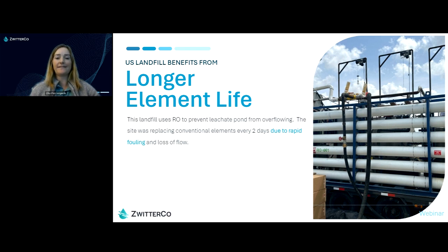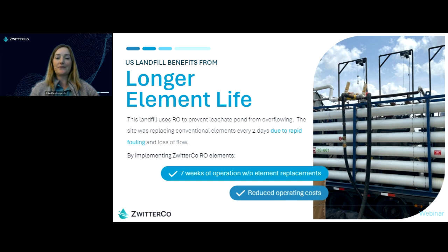Because the fouling at the site was so severe and they were replacing elements every other day, the site chose to implement ZwitterCo RO elements. By implementing ZwitterCo RO elements and by making a few operational modifications, the site saw some immediate benefits. The site was able to run for 7 weeks without element replacements.